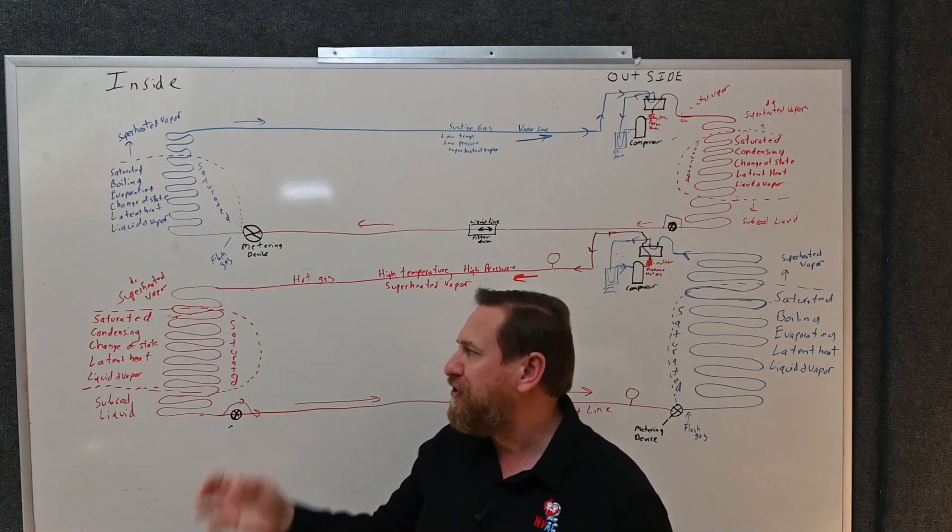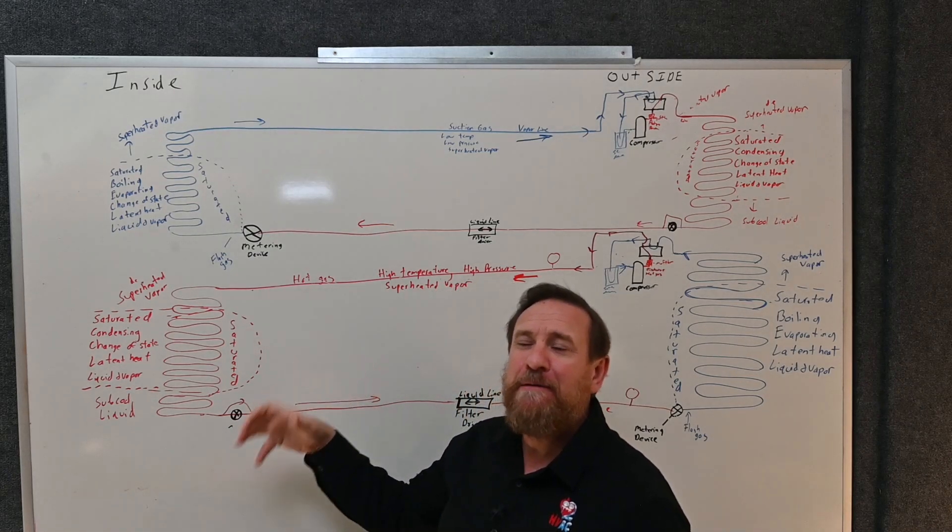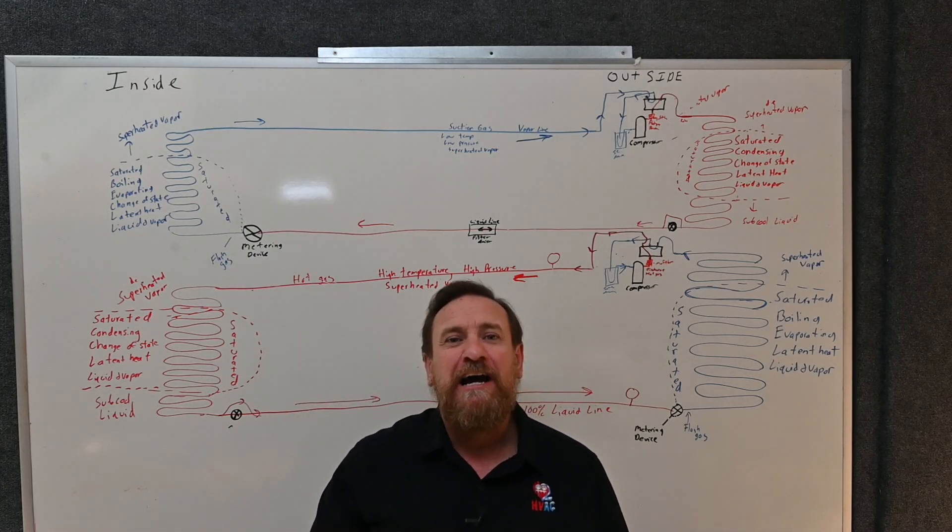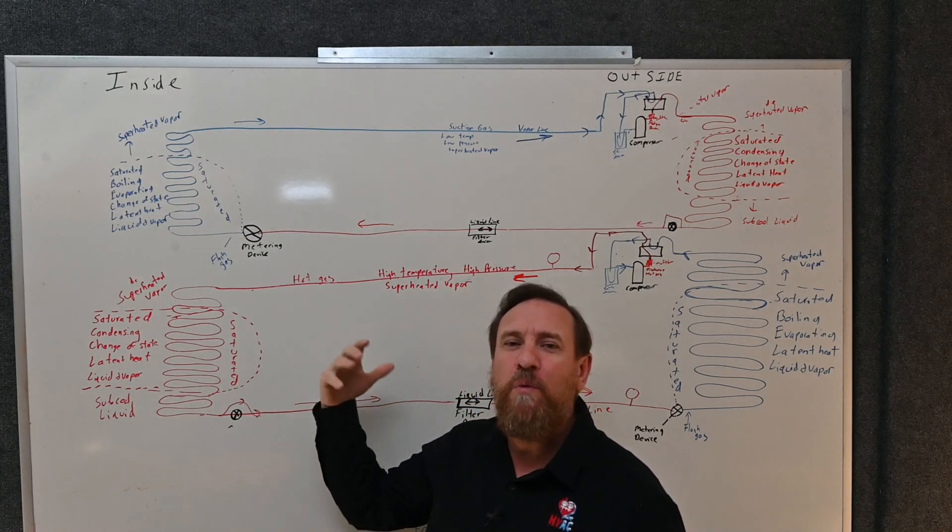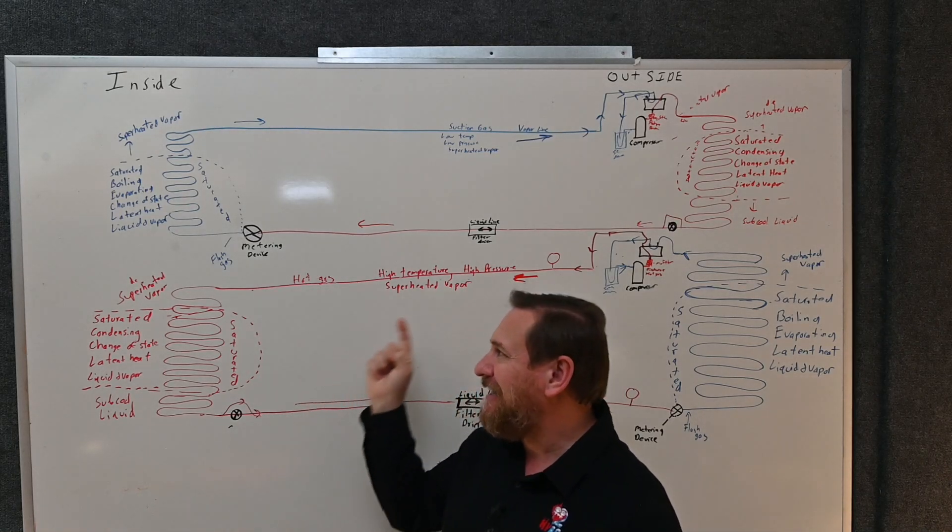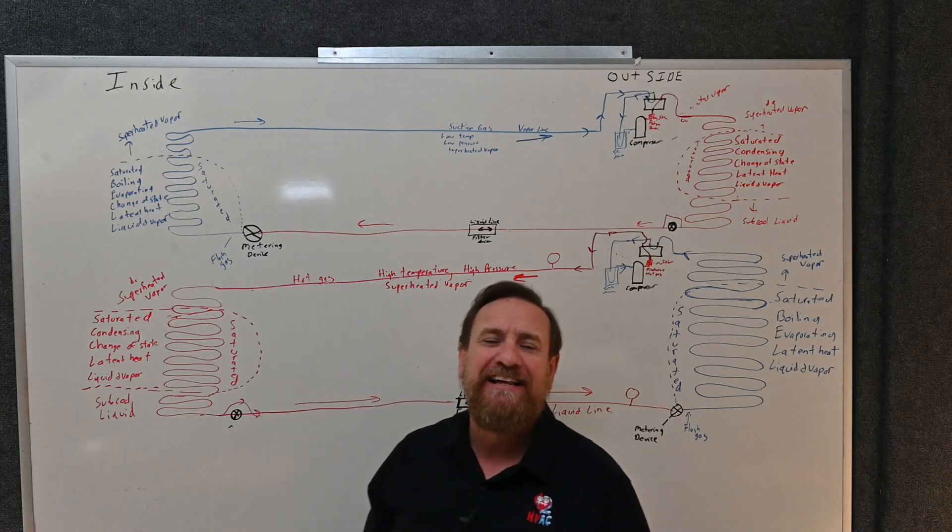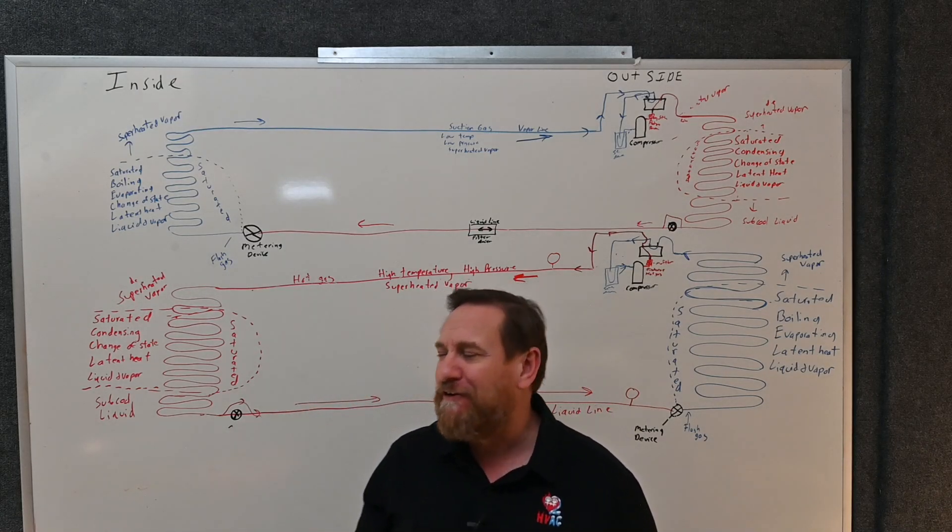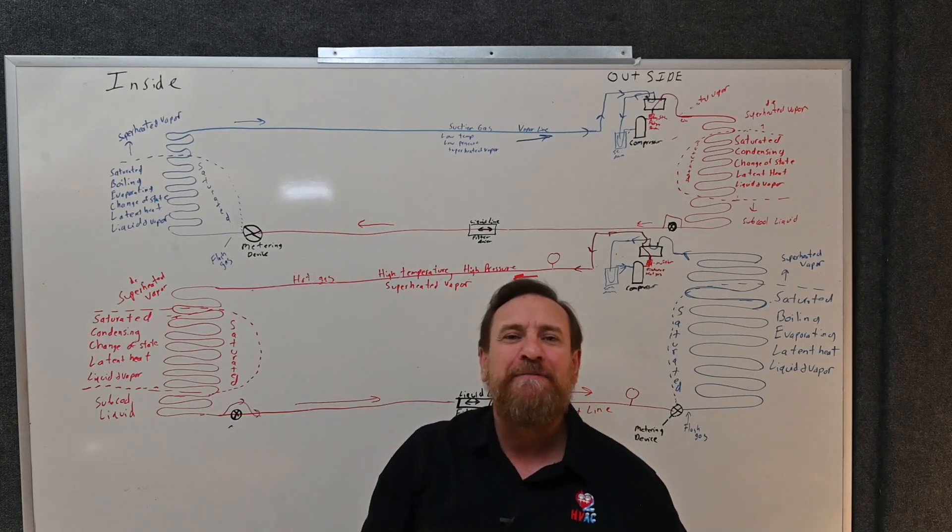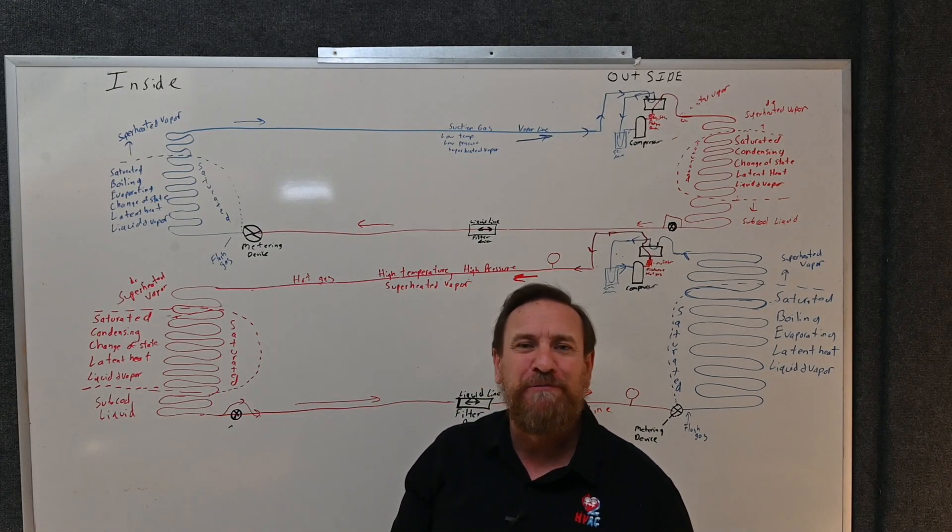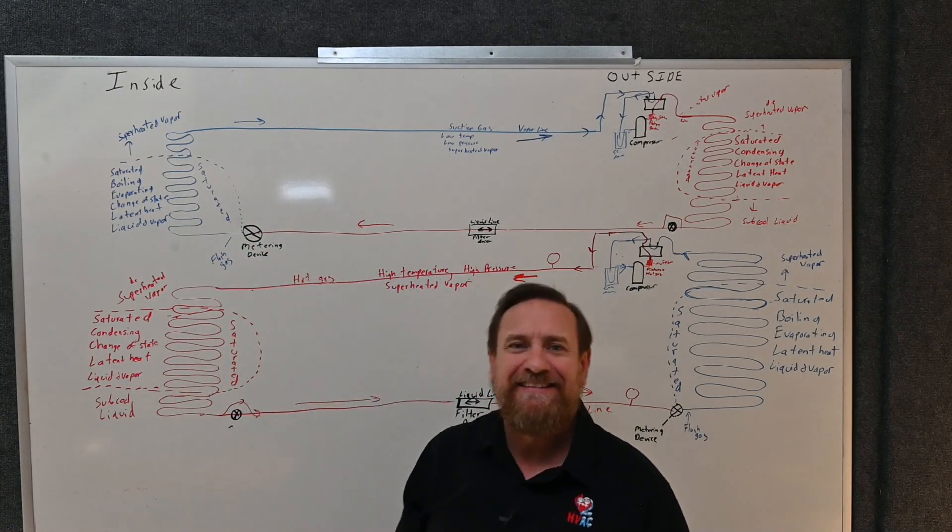It's always more difficult to charge the system in the heating mode because it needs less refrigerant. A lot of times it results in having to take all the charge out and then weigh that charge back in, taking into account the length of the line set. It can be much more difficult to charge that system in heating mode, which is why we want to make sure we use the correct manufacturer recommendations, the correct superheat and subcooling when we're charging in AC mode.